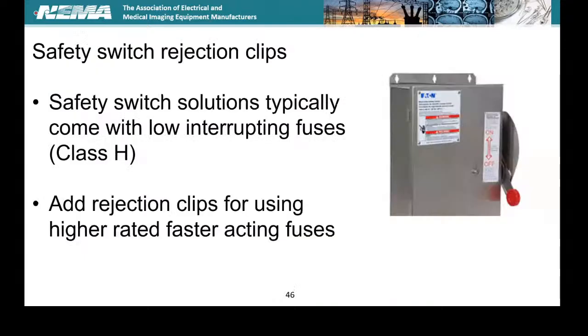And then you've got to think about where these go. The rejection clips. So what we're showing here from a NEMA perspective, we're saying, look, most of these switches will not ship with rejection clips. So they ship ready to handle a Class H fuse, which is non-current limiting. What you'd want to do is add those rejection clips and then put a more current limiting device inside this equipment, which offers, again, better protection for your equipment, better arc flash protection for your people, and lower or shorter downtimes and all that good stuff. Next slide.